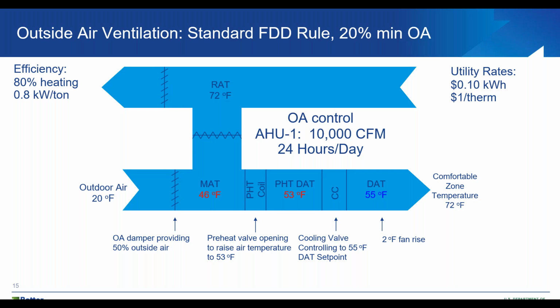Let's take an example. Under normal conditions pre-COVID, this is a schematic of a typical air handling unit. It has return air in it, it has outside air, and the economizer is able to provide different amounts of outside air down to a minimum of 20% outside air. In the normal flag, you see the mixed air temperature, the MAT, is 46 degrees. So the outside air damper is actually providing 50% outside air.